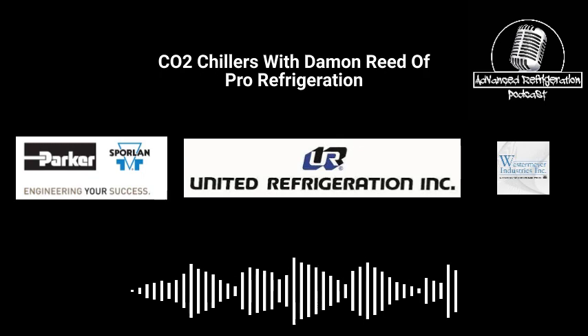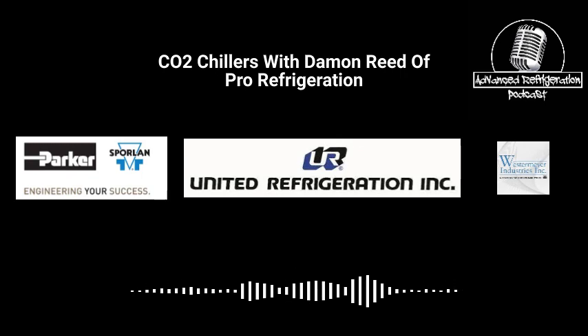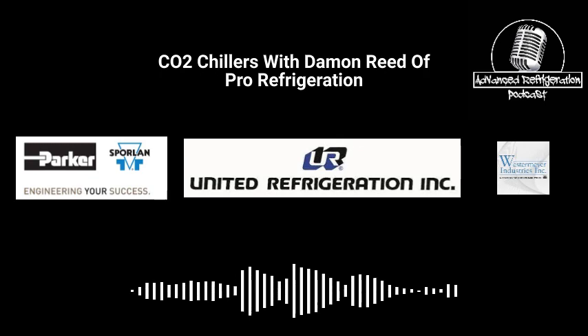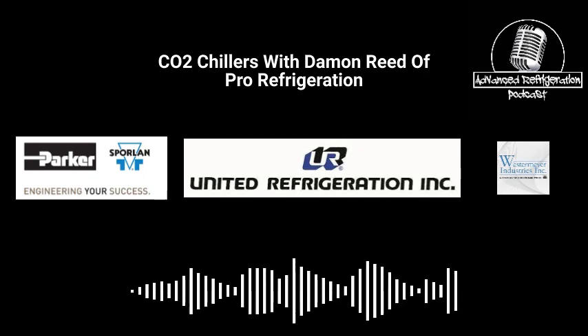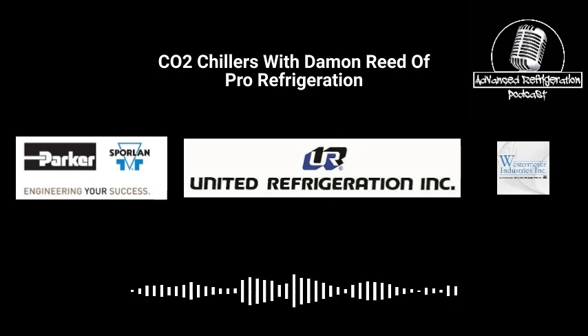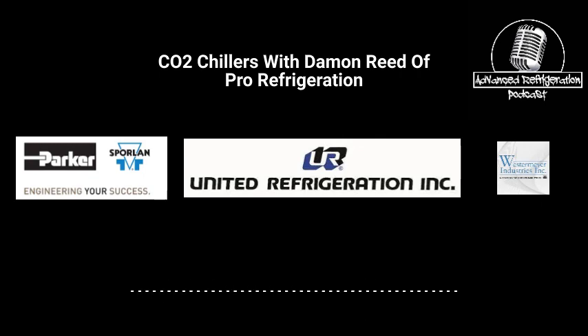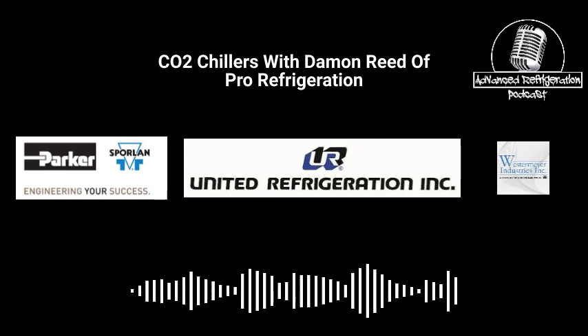Before, we did it one time with auto switchover and lead lag control on the backup. What you'd find is it depends on the application. If you're dealing with industrial refrigeration contractors, they're going to be a little more on top of stuff. When I'm working on other applications, a lot of times the system will automatically switch over to backup. Let's say the primary has a failure. Nobody pays attention to it, because their product's still cold.